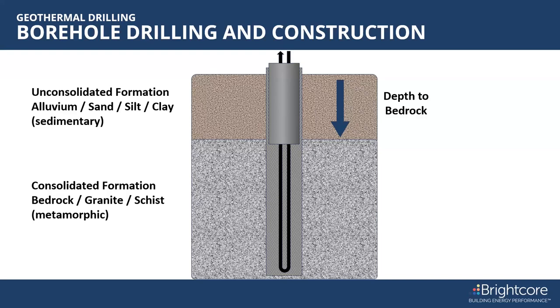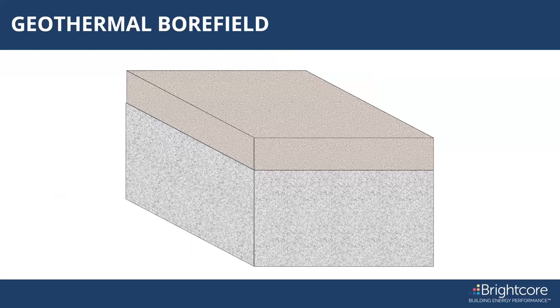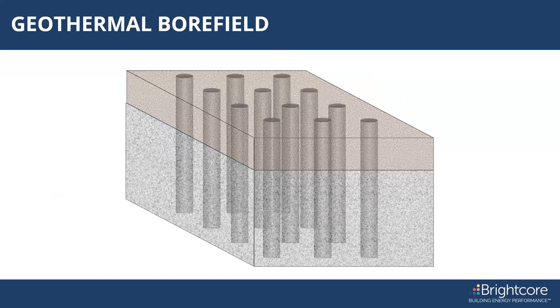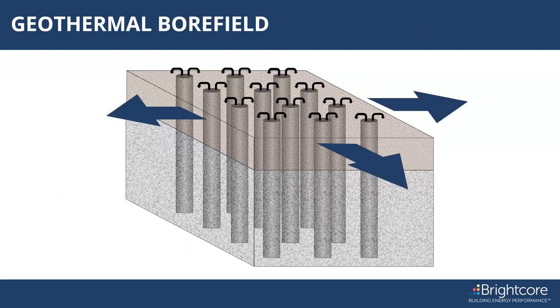In bore fields, you'll see holes offset in rows in a vertical field, with the loops connected via lateral trenching and backfilling. These are set it and forget it, piped over to a manifold that can be manipulated and run as needed. It's not one large loop going in and out of every hole, but circuits or branches, like a tire with various spokes, which allows the heat reservoir to stay in balance with building systems and needs, whether cooling or heating dominated.